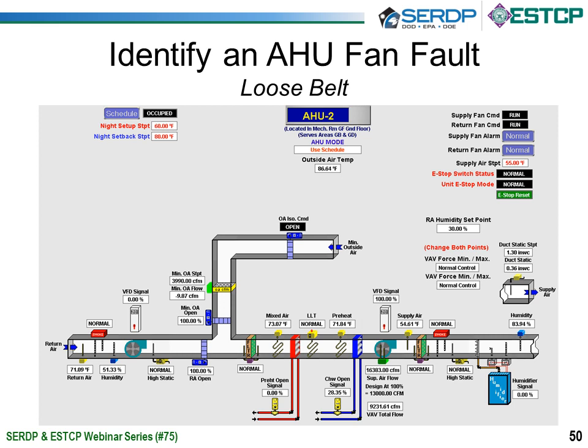I'm going to show you first detection of a loose belt fault. You can see a representation here that's from a building automation system. On the left-hand side at the bottom in the diagram, you see return air coming back from the spaces. In the middle branch that's rising from the main branch there, you see the outdoor air intake and associated controls. As you move to the right along the lower branch, you see heating and cooling coils, filter and so forth, and leading to the right is the supply air temperature after being cooled.